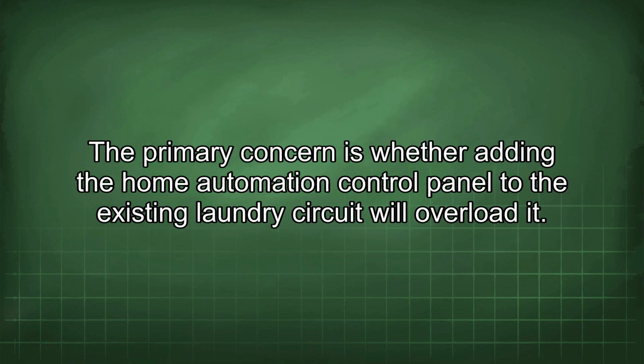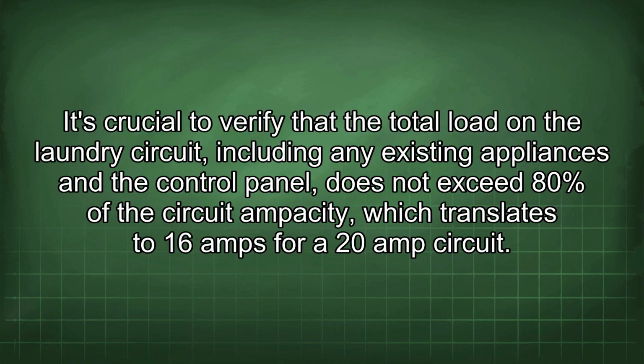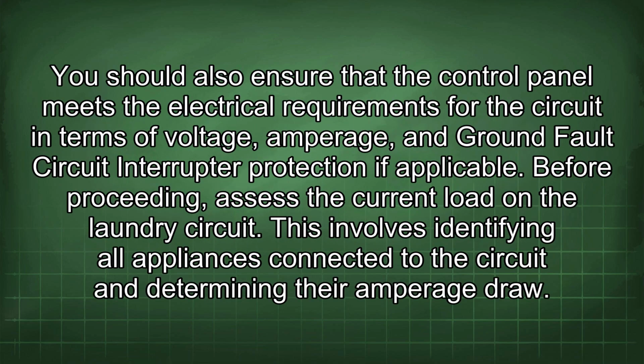The primary concern is whether adding the home automation control panel to the existing laundry circuit will overload it. It's crucial to verify that the total load in the laundry circuit, including any existing appliances and the control panel, does not exceed 80% of the circuit ampacity, which translates to 16 amps for a 20-amp circuit. You should also ensure that the control panel meets the electrical requirements for the circuit in terms of voltage, amperage, and ground fault circuit interrupter protection, if applicable.